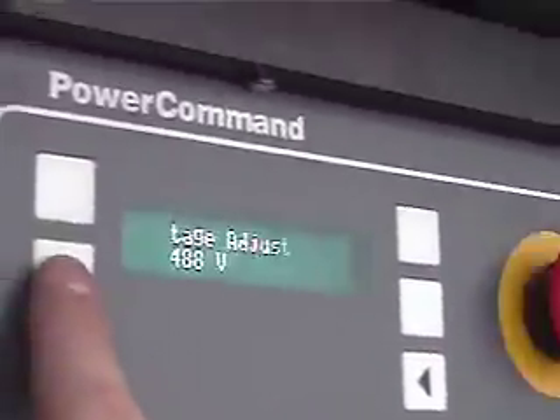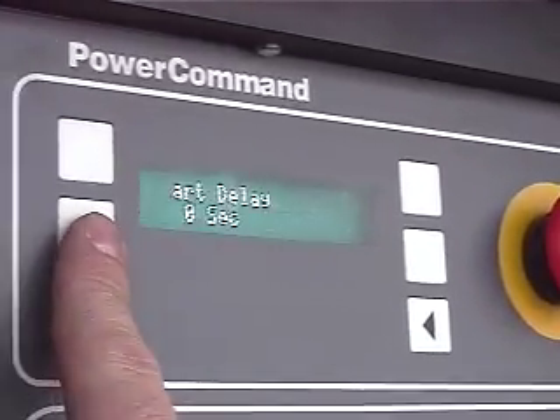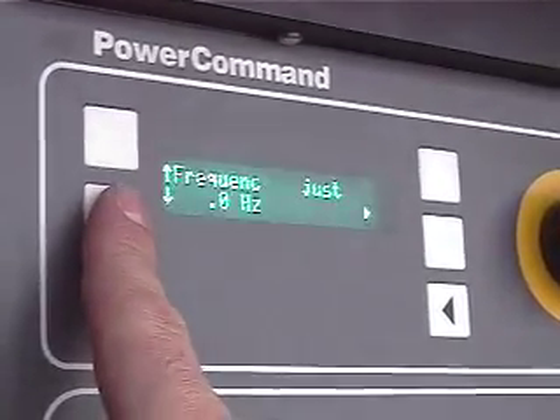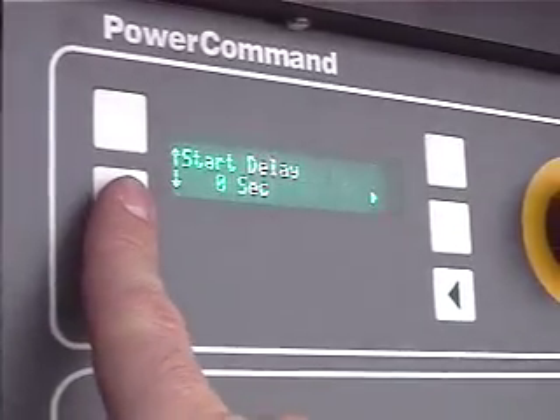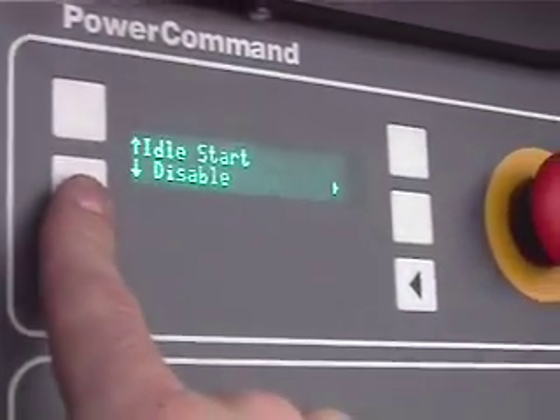So a lot of times, with 10 volts you'll see a difference in the light, how bright the light is or how dim it is. So we like to match the generator to what your utility power is. Here again you can just follow the arrows down: frequency adjust, that's basically turning the engine speed up or down a little bit; start delay, stop delay, rated to idle, and idle start.